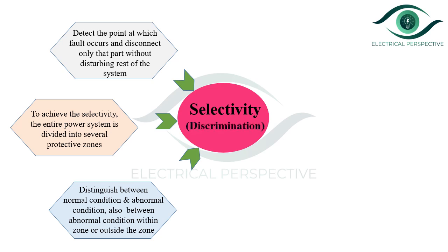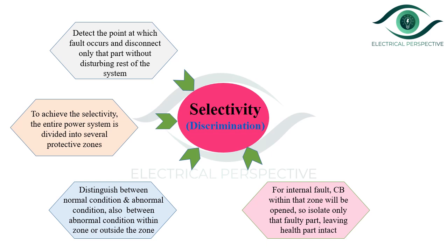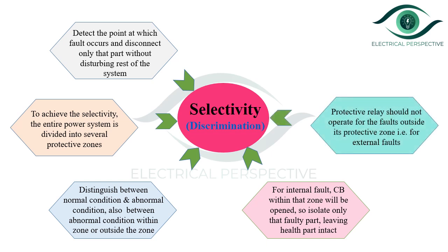This property is also known as discrimination. For an internal fault, the circuit breaker within that zone will open, isolating only the faulty part and leaving the healthy part intact. The protective relay should not operate for faults outside its protective zone, i.e., external faults. An internal fault is one occurring within the protective zone; an external fault is one outside it. The relay should operate for internal faults only to achieve selectivity.